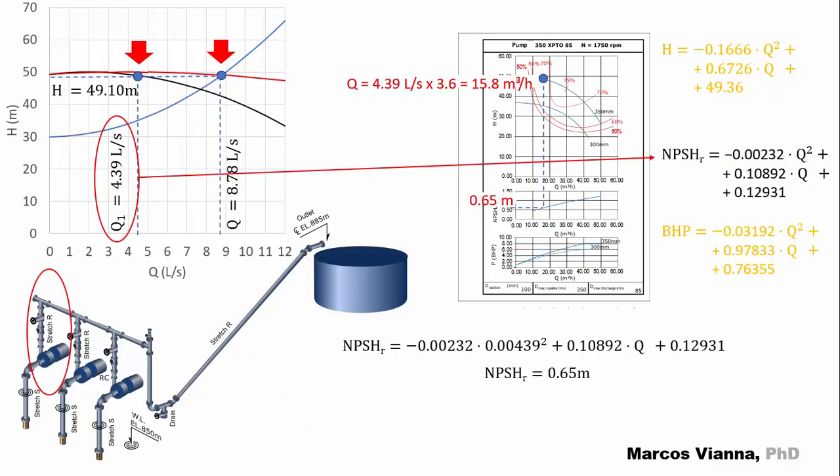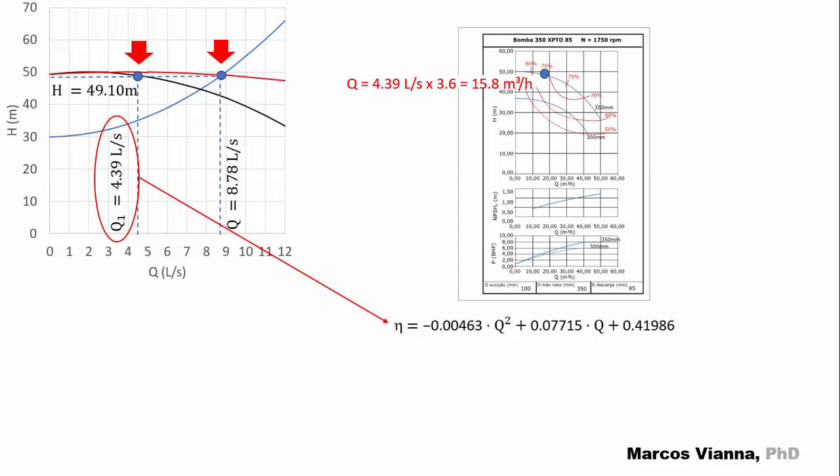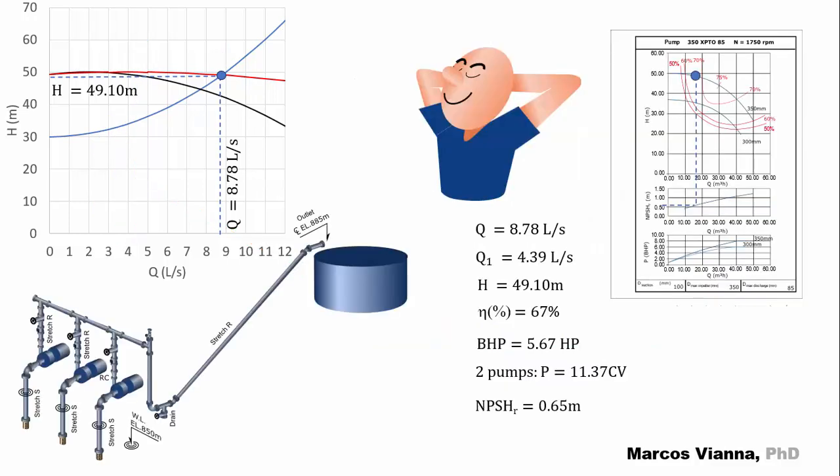And now, the required NPSH. It's just the same. We substitute the values and find 0.65 meters. I almost forgot! Here's the efficiency equation. As in the other cases, we substitute the values and find 0.67 or 67%. And so, we completed our task.